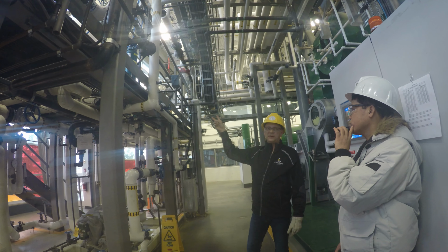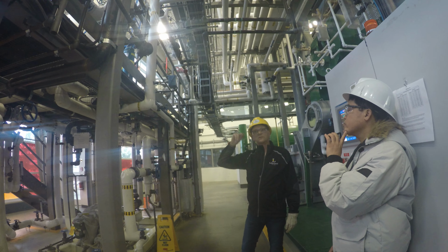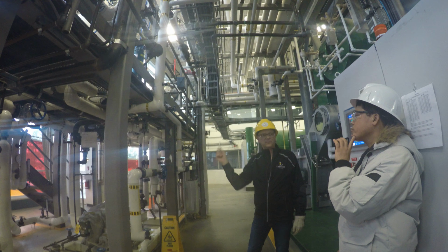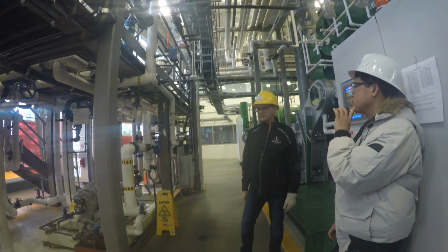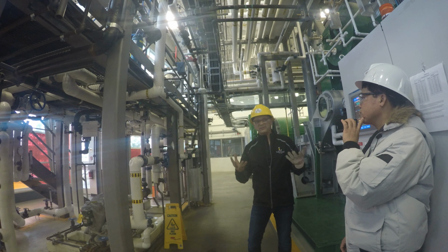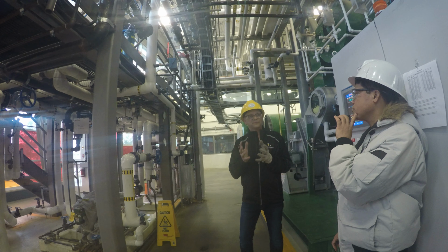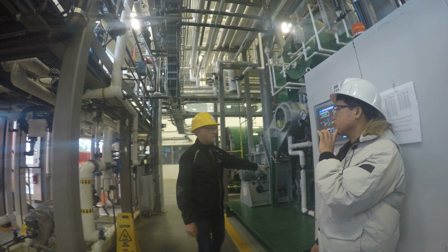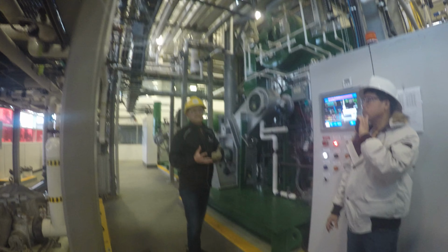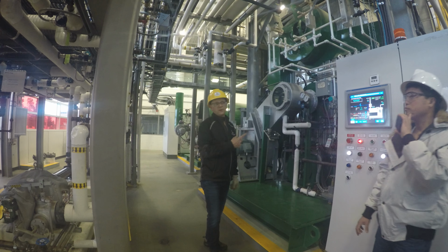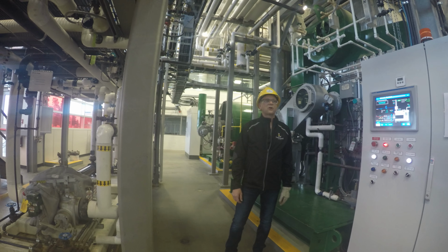We also inject chemical into the boiler. We put an oxygen scavenger in there, so with whatever the deaeration doesn't get, we put an oxygen scavenger in there. And we also inject a phosphate, which looks after any of the particulate that's in the water. It prevents it from scaling against hot surfaces. It helps it clump together, and then we just blow it out on a mud drum is what that's for. So it helps it precipitate down in kind of a sludge form, not a hard scale, and it gets blown out of the boiler.